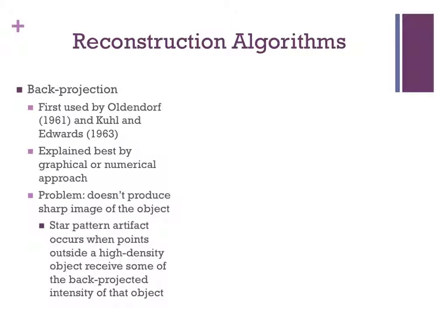One type of reconstruction algorithm is back projection. Think of 4 beams of X-rays that pass through an unknown object to produce 4 different projection profiles. The problem involves the use of these profiles to reconstruct an image of the unknown object. The projected data sets are back projected to form corresponding images, and then the reconstruction involves summing these back projected images to form an image of the object.